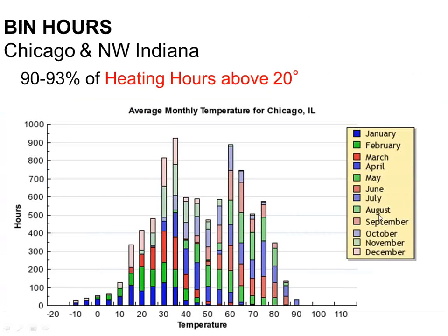If I look at it graphically, because some people are wired that way a little bit better, you can see visually, if I added up all the blocks of hours throughout the year at different outdoor air temperatures, I got a lot of hours that are in that 20 to 65 range, right? The bulk of my hours, like we said, 90+% of them are in that range. I have very few hours where it's really cold, right? And the likelihood of it being -20 on a percentage basis is 0. It could happen, but percentage-wise, it's 0.